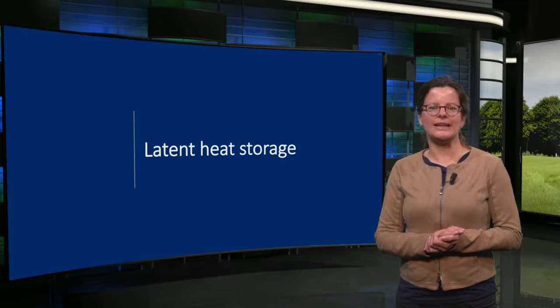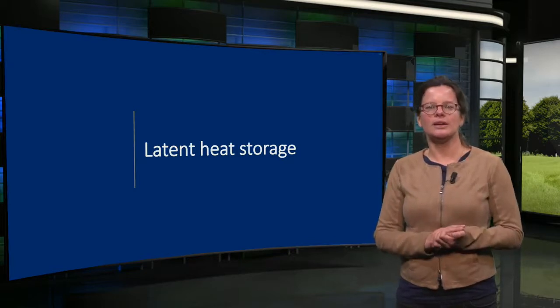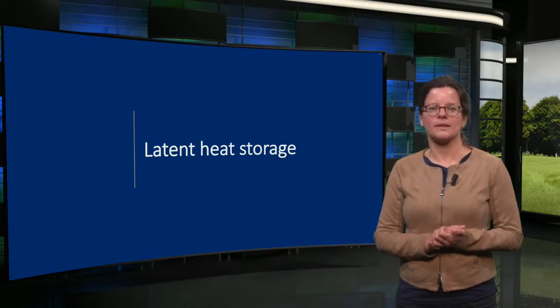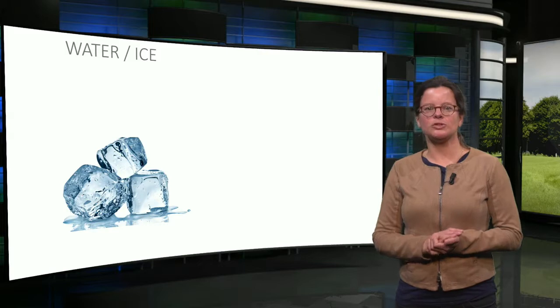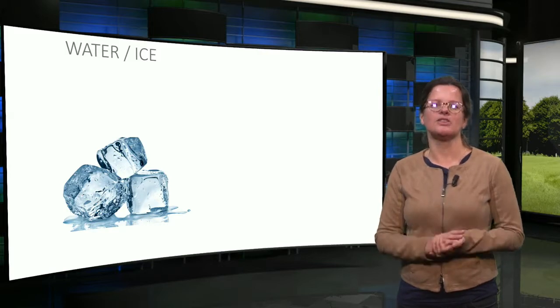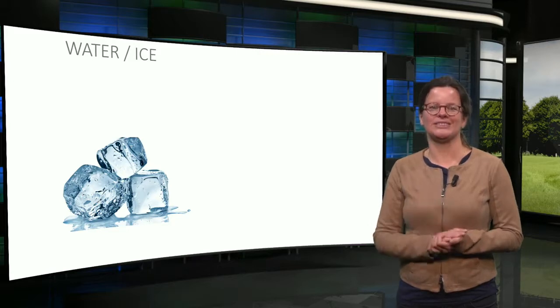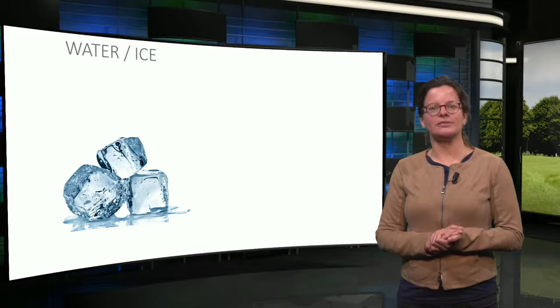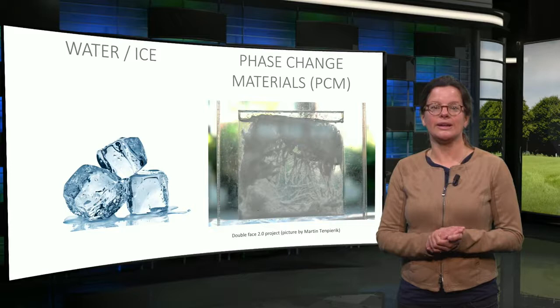Now I would like to briefly mention latent thermal energy storage. In the change of phase of a material, for example from liquid to solid or from solid to liquid, a lot of heat is required or released. This phenomenon can be used to store energy. The most well-known phase change material is obviously water. In the phase change from water to ice, the energy released is 80 times as much energy as cooling down the same amount of water with 1 degree Celsius. For the built environment, various other types of phase change materials have been developed and are still being developed. These usually have a higher melting point, which means much energy can be stored at these temperatures.